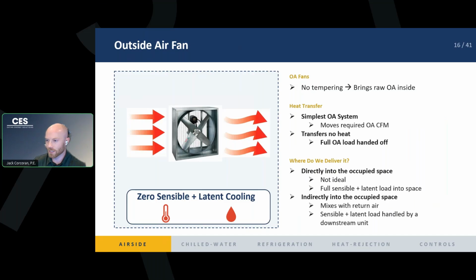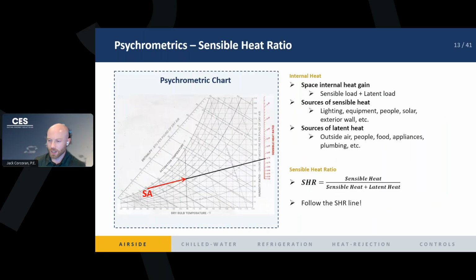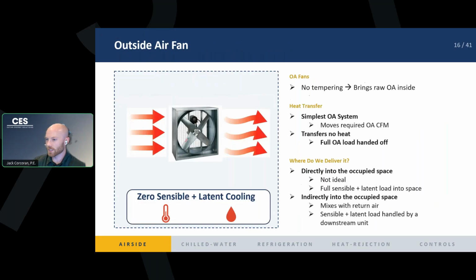If you go back to this chart, instead of having our supply air being way, way down to the left of the chart, it's going to be way high up on the right side. It's 95 degrees dry bulb. You move to the right and then you move up to 75-degree wet bulb. It's going to be a very, very warm space. And, intuitively we know that, right? If we're just dumping hot, wet air into our space, that raw outside air is going to cause the room to get hot and get high humidity.